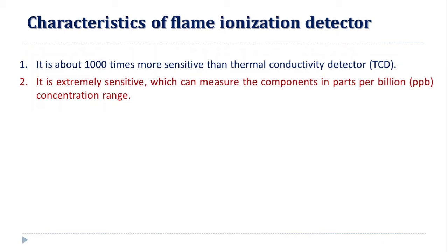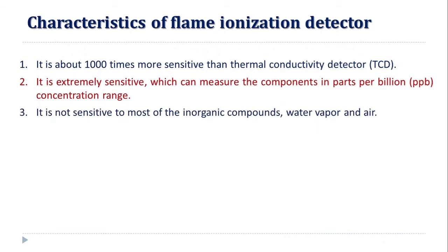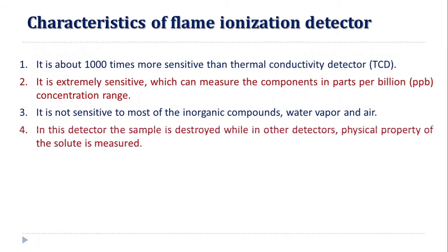Despite being this sensitive, the flame ionization detector is not sensitive to most of the inorganic salts. So this is a limitation. It is not sensitive to inorganic compounds and water vapors as well as air. What about the thermal conductivity detector? It is sensitive to organic as well as inorganic compounds. But the limitation for the flame ionization detector is that it is not sensitive to inorganic substances.